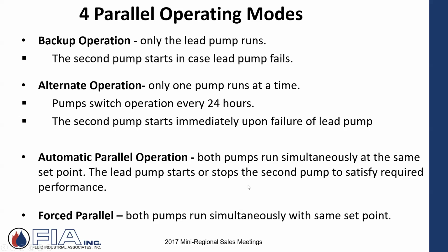It's been a long day, and you guys are exhausted, so I'm going to answer it for you. A quick answer would be, hey, George, that depends on the delta T, right? That's the quick answer. So say I did a heating system, 20-degree delta T, 300 GPM, that's 3 million BTUs. That's a pretty good sized plant. If I put 2 of them in parallel, I get 600 gallons a minute. I got 6 million BTUs with 2 of these pumps that are sitting downstairs that are very configurable, so it's not limited to really small. You could get pretty aggressive.